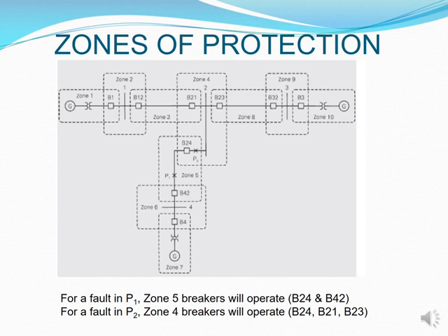Your circling up, always you need to have equipment accompanied by a circuit breaker. So where before in your previous slide you could see that your generator was followed by a circuit breaker, in this instance your generator goes straight into a transformer, and only then you have a circuit breaker. It therefore means that you cannot assume that your generator alone can be a zone.